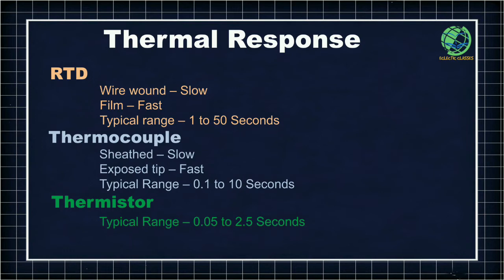Depending on construction type, wire-wound RTDs are slow while film RTDs are fast. Thermocouples can be of two types: sheathed or exposed tip. With an exposed tip, the junction is heated directly from the temperature source. In a sheathed thermocouple, the tip is inside the sheath, so it gets heated only after the outer sheath heats up — meaning sheathed thermocouples have a slower thermal response, while exposed-tip thermocouples have a faster thermal response.